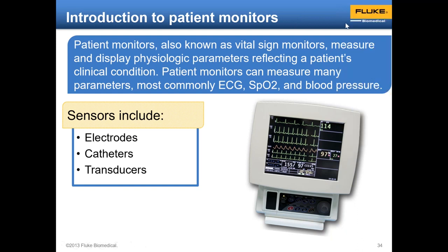So now we're going to talk about doing electrical safety testing on patient monitors. And actually, this comes from the Medical Device Quality Assurance course series. Excuse me, one moment, Jerry, if you could slide your GoToWebinar window. There you go. Perfect. Thank you. This comes from our MDQA course series, and we're focusing on the entire test for patient monitors, but we're going to try and focus only on really the electrical safety part of it. Remember, there's a lot more testing that needs to be done on the patient monitor besides just electrical safety testing, but our focus today is about just the electrical safety tests and nothing else.